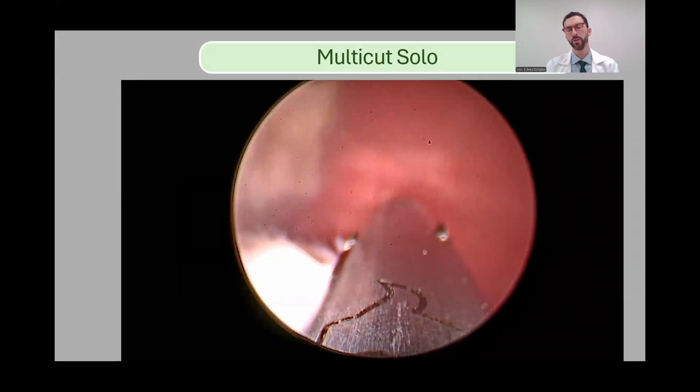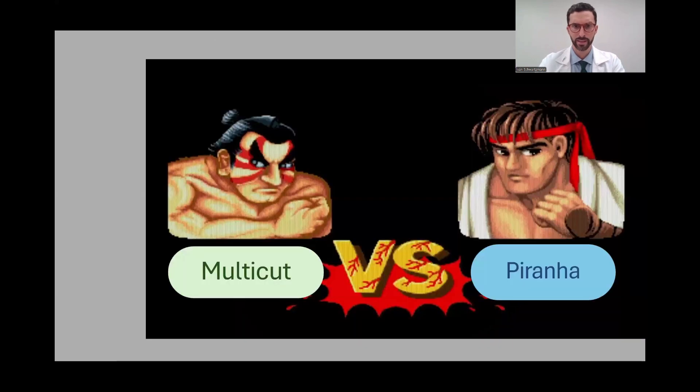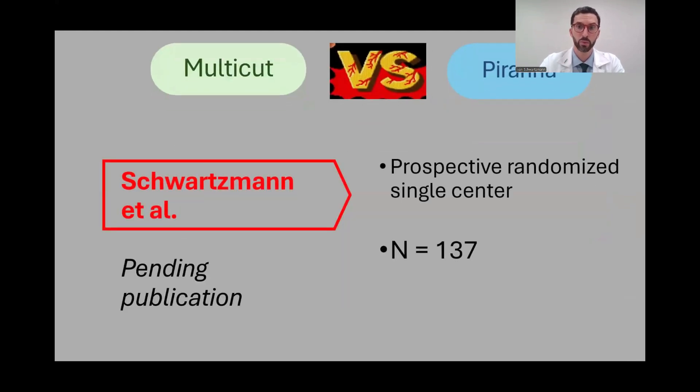There are some tips for improving suction with the Multicut: morcellate standing up so gravity helps water flow from the patient down to the device and drainage, and maintain a good position not too far from the bladder wall to avoid a sharp angle between the handpiece, blades, and adenoma. There are currently no published head-to-head comparisons for the Multicut, but we performed one — a head-to-head comparison between Multicut and Piranha in a prospective randomized single-centered study at Fundación Puigvert in 137 patients, pending publication.